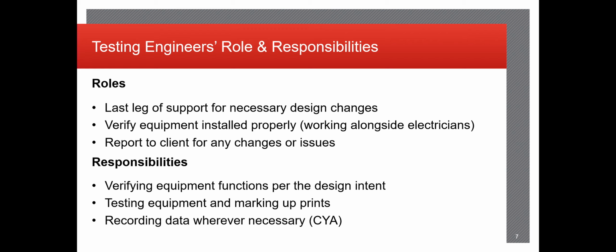To get started, a brief explanation of the major roles and responsibilities of the testing engineers in the field. The field guys are usually the last leg of support for necessary design changes. If we get a print out in the field that has incorrect functional verification, it just doesn't work, or it actually doesn't even exist out in the field, such as equipment that was never ordered, isn't fit to the right specs, or just doesn't work at all. We're usually the last leg for any design changes, reaching out to the engineers that put the design package together and getting their support on what the next steps would be.